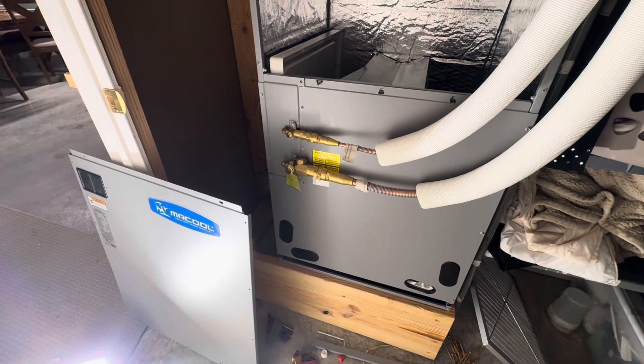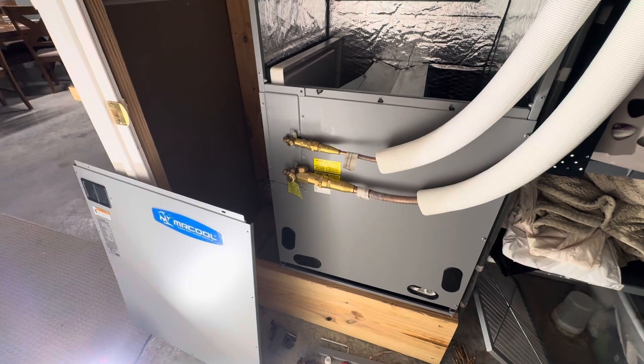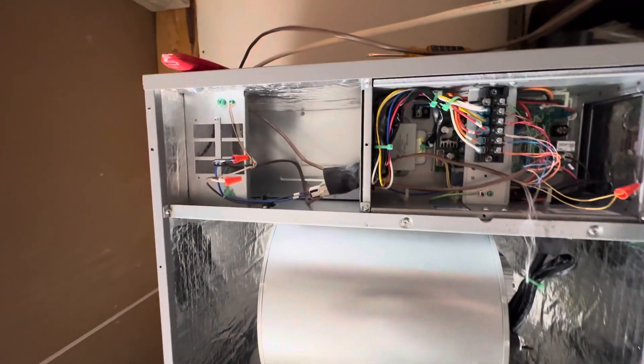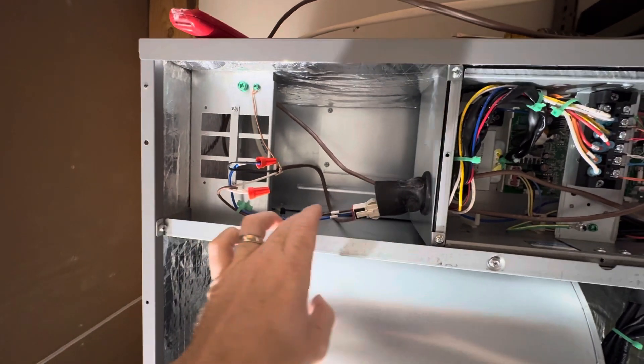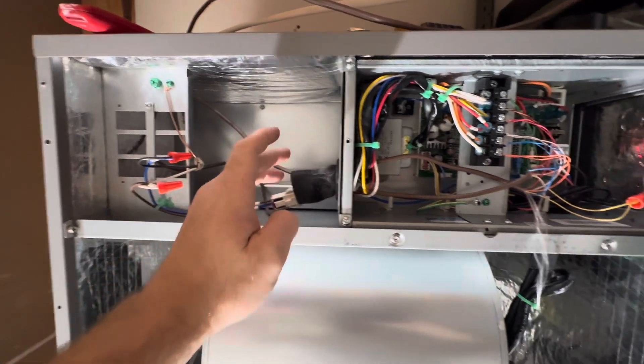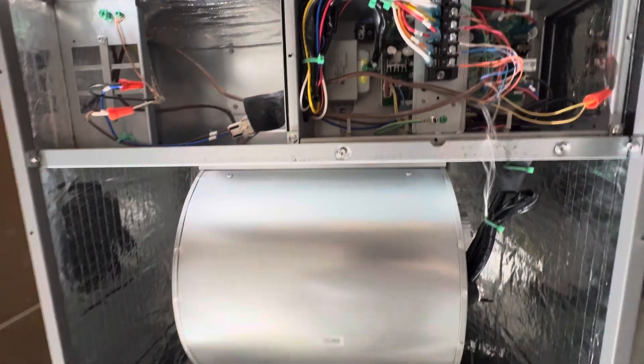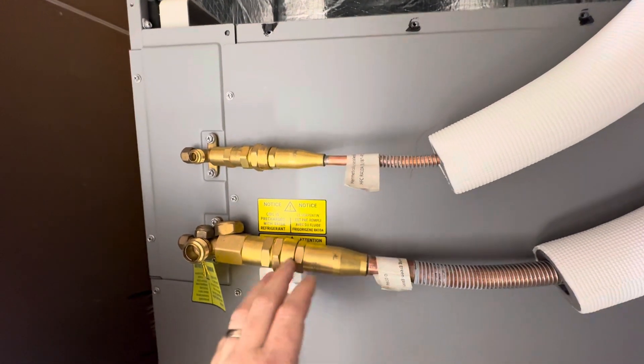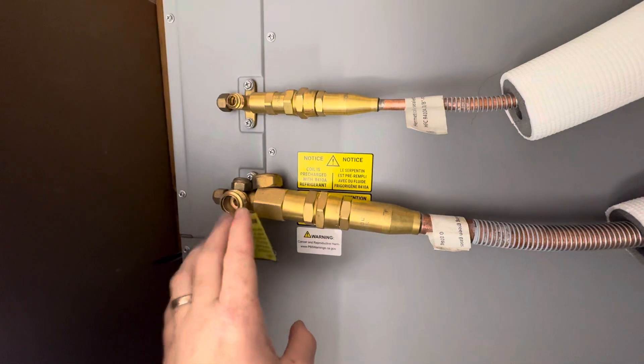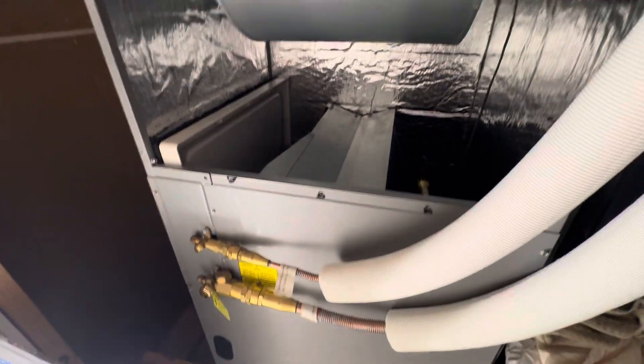We've got a MRCOOL universal 4 to 5 ton heat pump split system that makes DIY installation very easy with the line set. On the inside, you need to install power — a 15 amp circuit — with brown and blue wires coming out here. Thermostat wires go right here, simple. You can look up videos on that. Then your line set, and the last thing will be your drain. So on the inside: power, thermostat, line set, and drain.